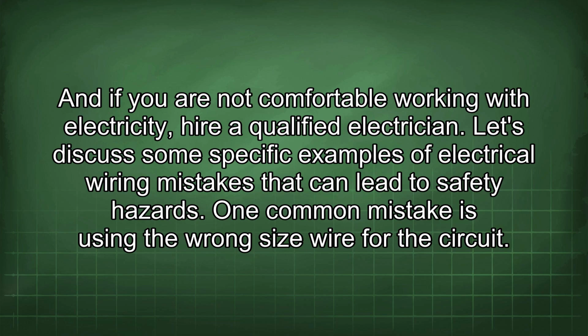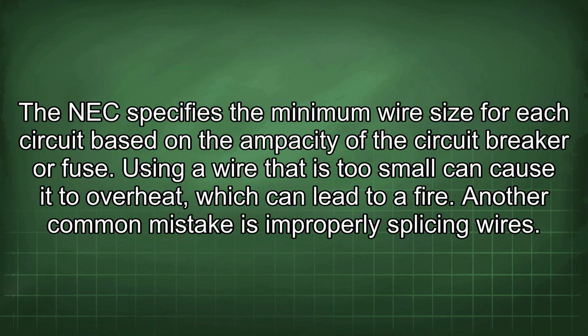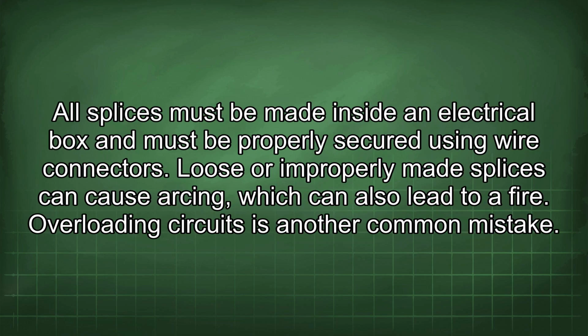Let's discuss some specific examples of electrical wiring mistakes that can lead to safety hazards. One common mistake is using the wrong size wire for the circuits. The NEC specifies the minimum wire size for each circuit based on the ampacity of the circuit breaker or fuse. Using a wire that is too small can cause it to overheat, which can lead to a fire. Another common mistake is improperly splicing wires. All splices must be made inside an electrical box and must be properly secured using wire connectors. Loose or improperly made splices can cause arcing, which can also lead to a fire.